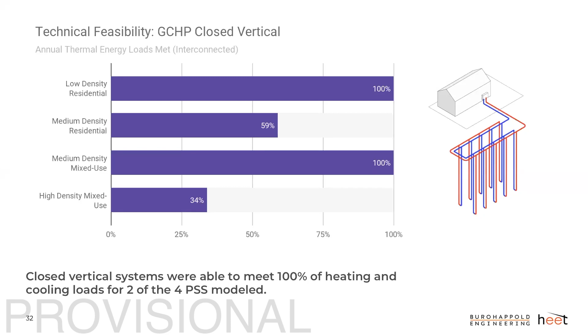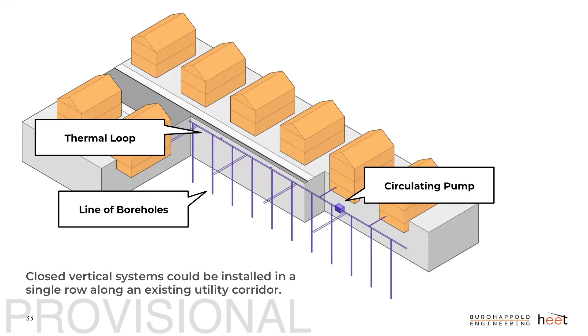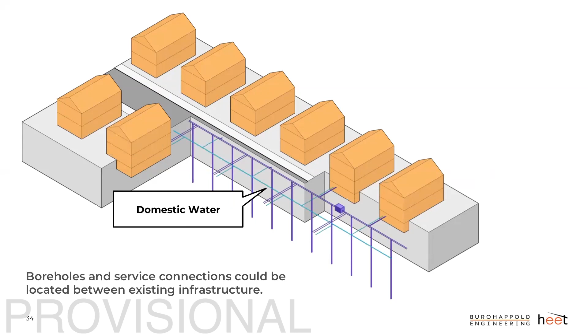So what does it look like? This is a generic model of what a vertical system might look like in a utility right of way. We have this horizontal thermal loop with service going to each of the homes or buildings, and a line of boreholes that are 20 feet on center. Each borehole has a U-shaped tube that goes down and back, circulating heating and cooling to each building. It can coexist with other infrastructure, even a separated sewer, fitting somewhat easily between these things.